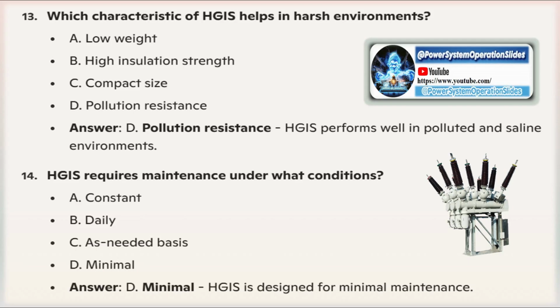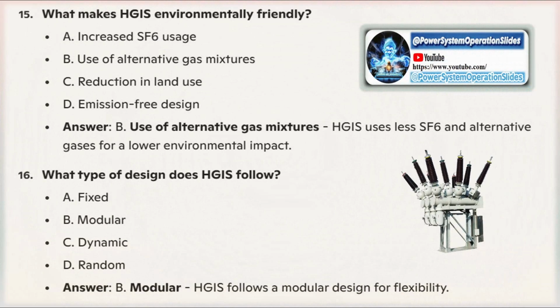This hybrid switchgear includes a vacuum interrupter in a gas-filled sealed tank, offering flexibility and customizability. It can be used for extensions or substitutions in traditional substations with air-insulated busbars. Hybrid GIS switchgear advantages: air-insulated busbar, inexpensive and reliable, assembled quickly without SF6 handling, making it environmentally friendly.